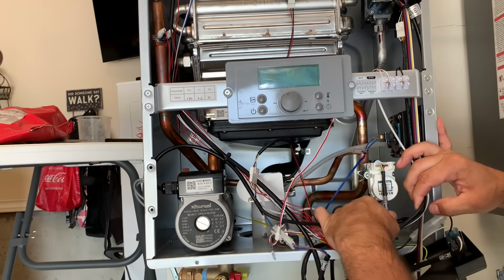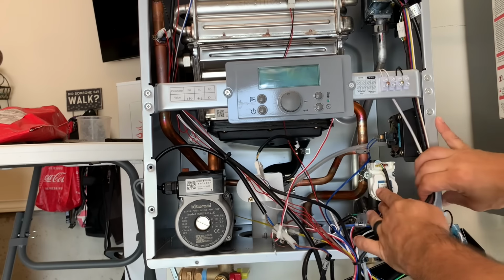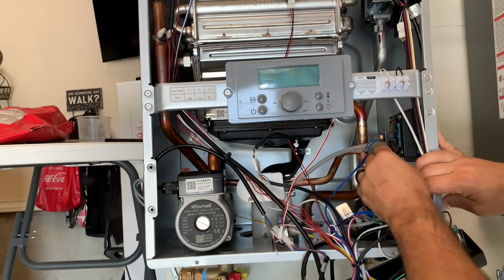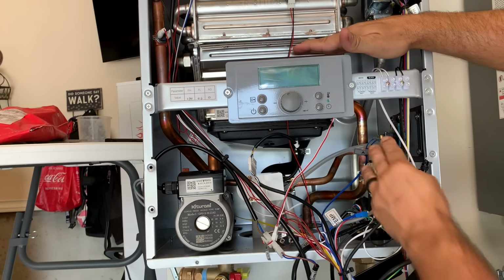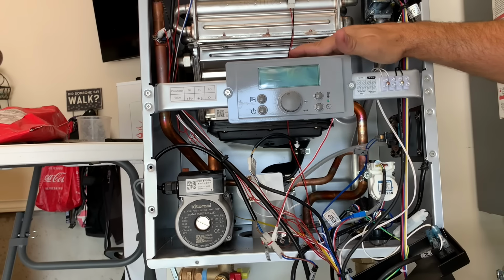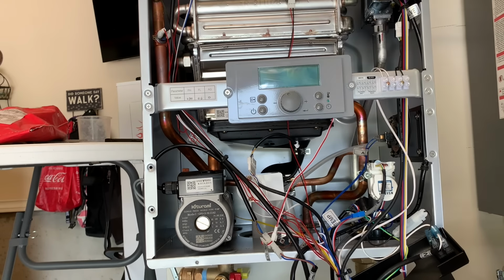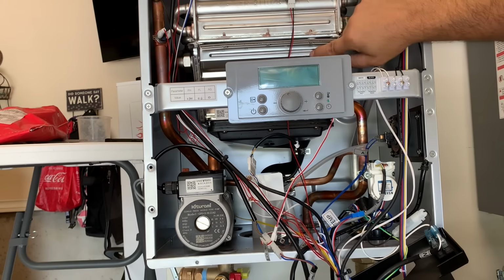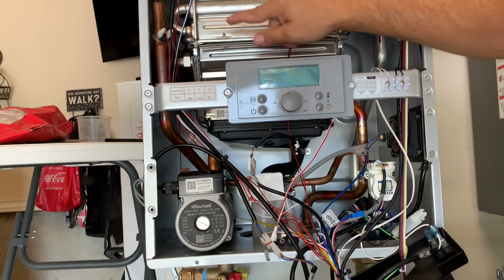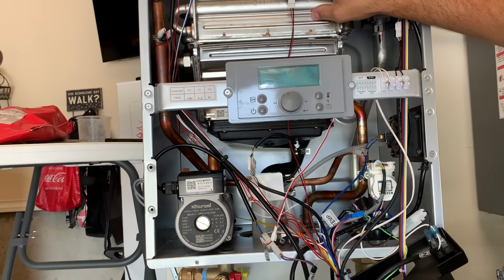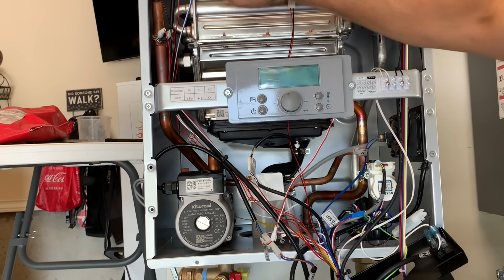Here's your water inlet. Water will come in here and it will go up and it will start getting warm through the secondary heat exchanger. Remember, this is a down fire burner, okay? So we're going to do the secondary heat exchanger. Then we're going to come up to the primary. Water will get hot and it'll exit right down through there and out.